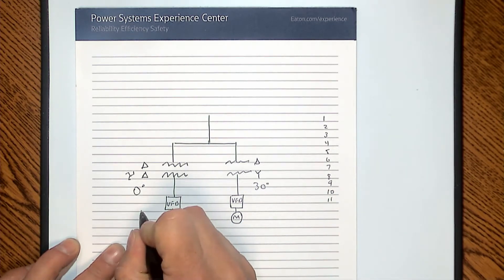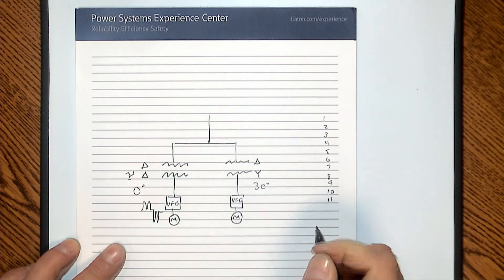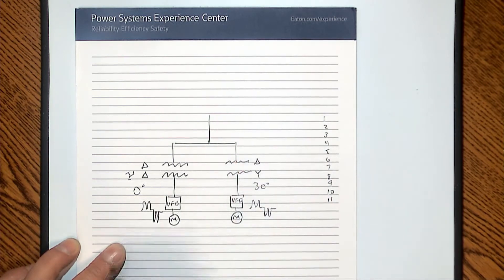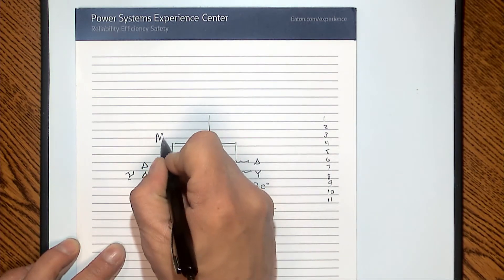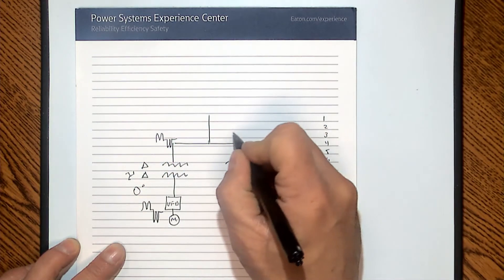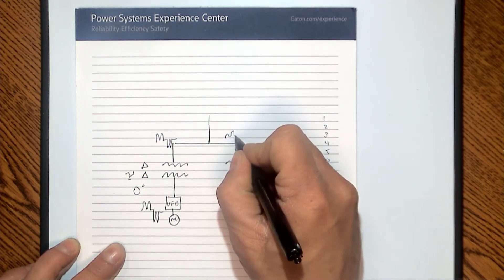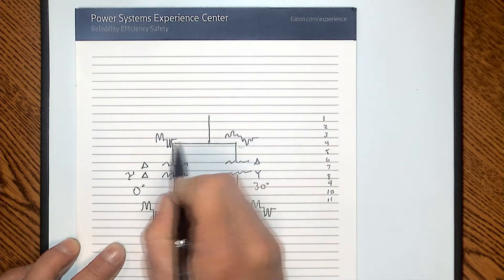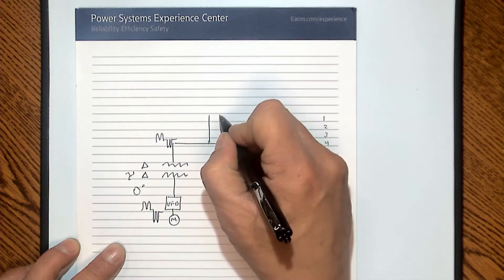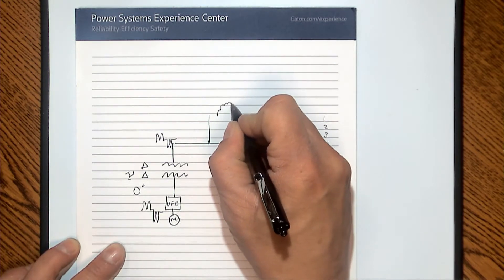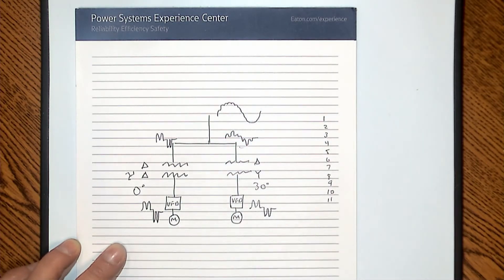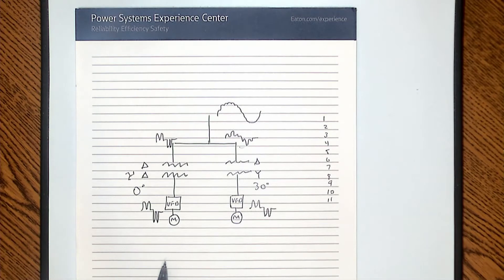The same harmonics come out of these drives as we saw before. The transformer with zero degree phase shift passes the harmonics through unchanged. The other transformer has a 30 degree phase shift, so the waveform looks a bit different. When you add these two together, we get what is now not a six-pulse system but rather a 12-pulse system, and we end up with a current that looks fairly linear. Let me show you that in the actual waveforms from the two drives.